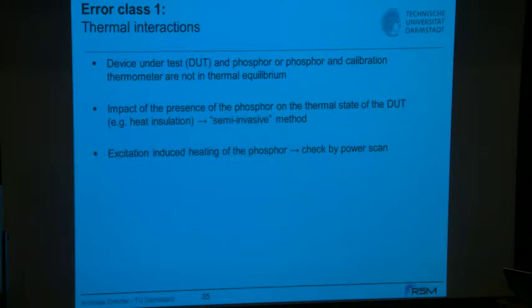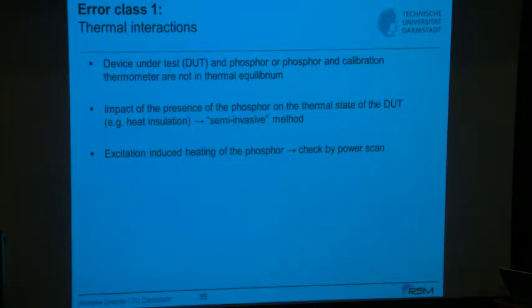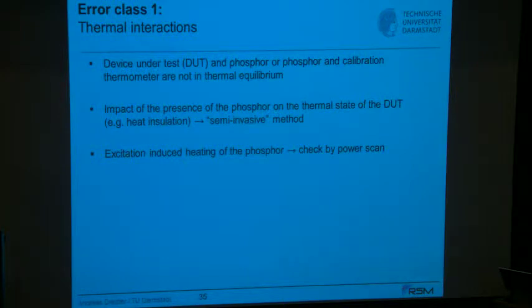Error class one is heat transfer. The phosphor coating and the calibration thermometer may not be in thermal equilibrium, and the phosphor and substrate may not be in equilibrium during strong temporal variations. If you have a phosphor made of ceramics, even a 10-micron-thin coating acts as heat insulation. In that sense it is not a non-intrusive method — I call it semi-invasive — and this matters most if you have fast changes in surface temperature.